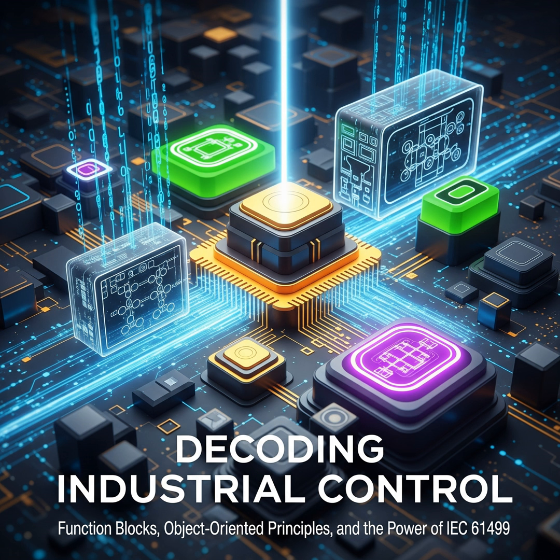Then the function block instance is the specific individual named copy. It's a realization of that blueprint. It gets all the attributes defined by its type. And making one is called? Instantiation. That's the process of creating that unique functional object within the system from the type definition. Right, instantiation. And this leads to something critical, especially when you're talking industrial scale. The standard lays out a very clear naming structure. You use the application name, any sub-application name, and then the specific function block instance name.